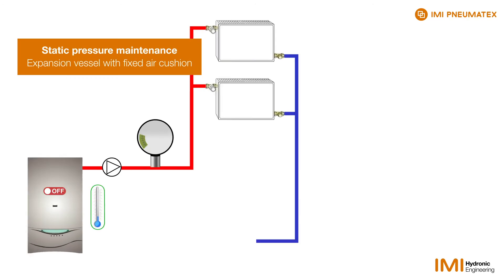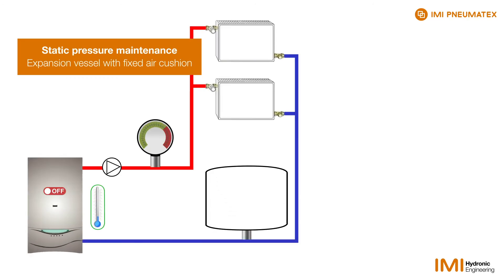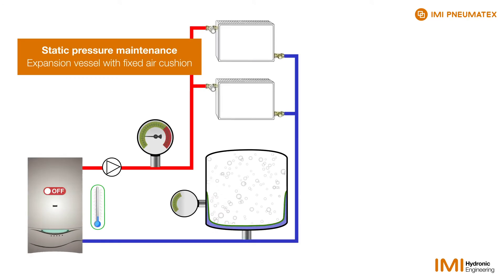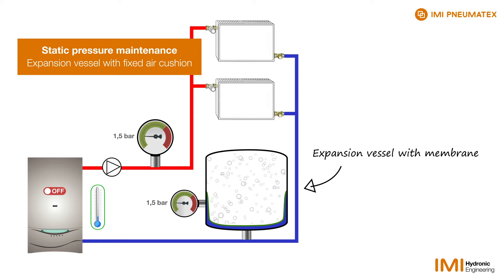We are looking at a heating plant that is protected by a static pressurisation system with a membrane expansion vessel. The manometer indicates a pressure of 1.5 bar in the system's cold state.